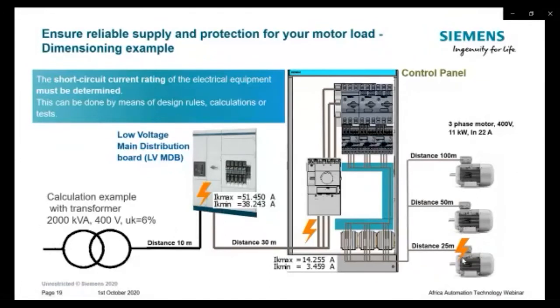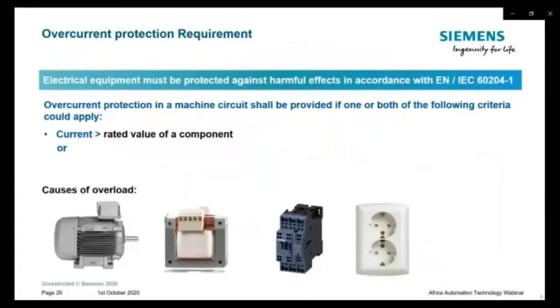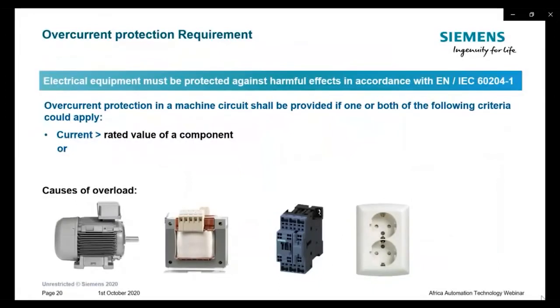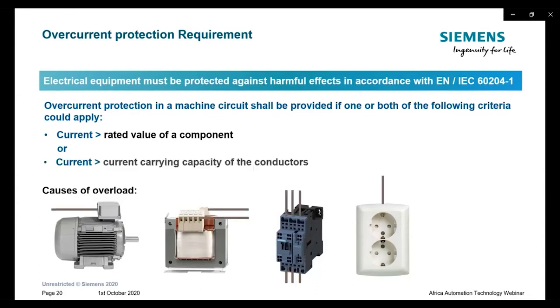Target is now to do the right dimensioning and engineering for the control panel devices and for the load feeders to withstand the short circuit current and to ensure reliable operation during load currents. Electrical equipment must be protected against harmful effects in accordance with the European or International Standard 60204-1. Overcurrent protection in a machine circuit shall be provided if one or both of the following criteria could apply. So the current can be more than the rated value of the component, or the current can be more than the current carrying capacity of the conductors.